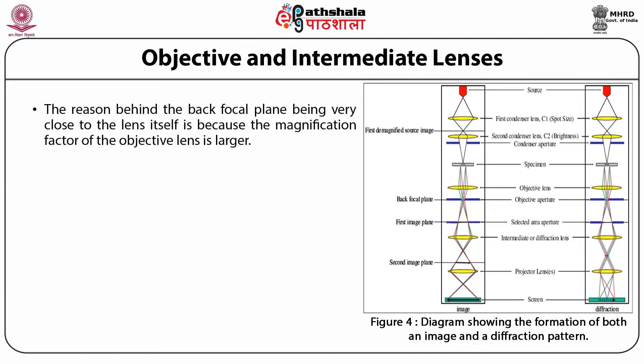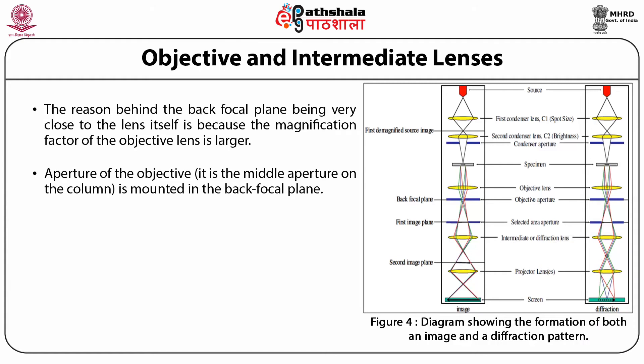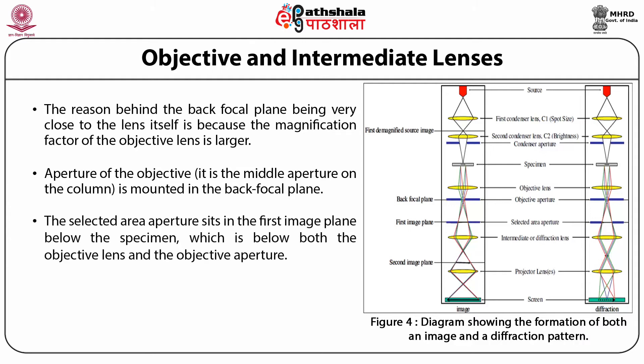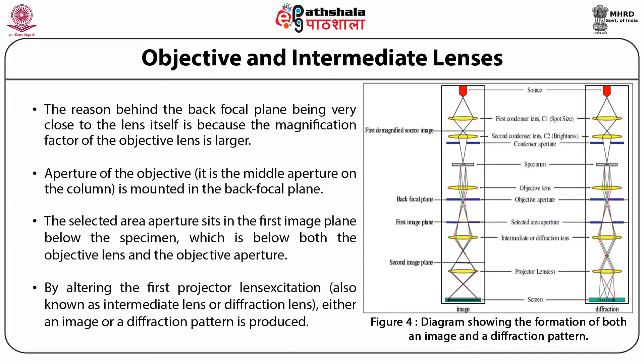Next, the objective and intermediate lenses are discussed. The back focal plane is very close to the lens itself because the magnification factor of the objective lens is large. The objective aperture, which is the middle aperture on the column, is mounted in the back focal plane. The selected area aperture sits in the first image plane below the specimen, below both the objective lens and the objective aperture. By altering the first projector lens excitation, also known as the intermediate or diffraction lens, either an image or a diffraction pattern is produced, as shown in figure 4.